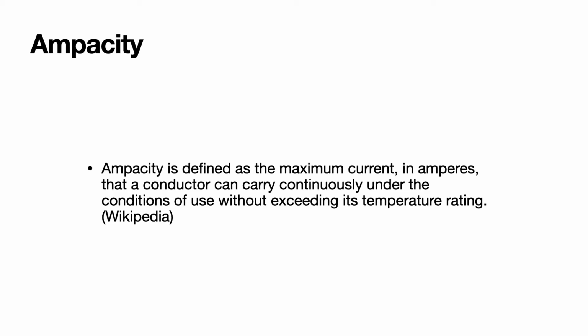The measurement is ampacity, or the number of amps that a circuit, a wire, a circuit breaker, etc., can carry, the capacity for carrying current. It's measured as the maximum current that a conductor or a circuit can carry continuously without exceeding its temperature rating. Buried in that is an observation that when you pass current through a wire, there is inevitably a little bit of heating, because every wire has some resistance, and the resistance causes the heating as the current passes through the wire.